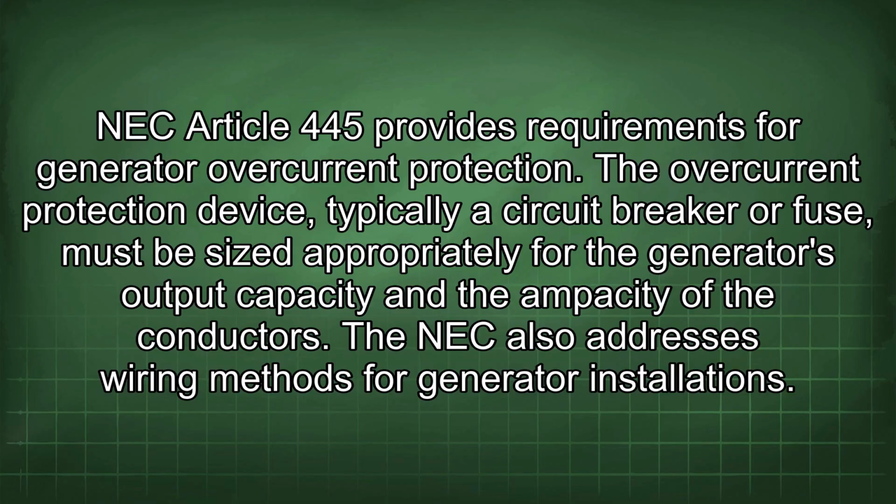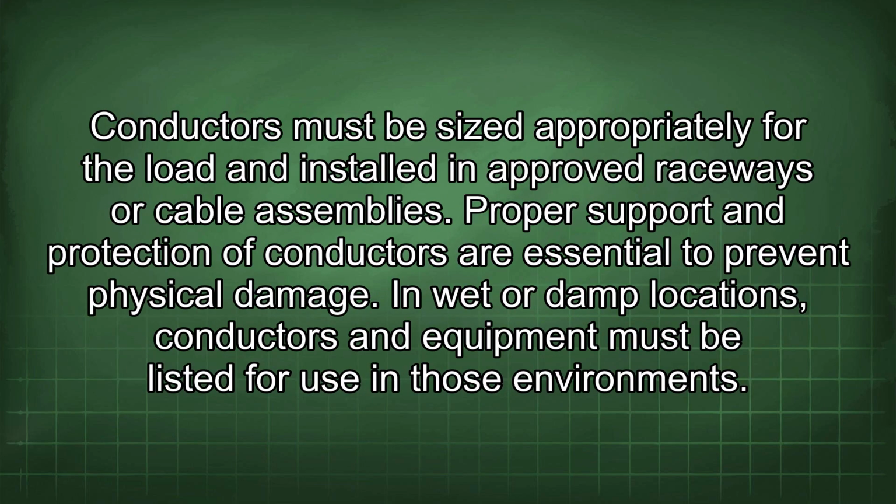The NEC also addresses wiring methods for generator installations. Conductors must be sized appropriately for the load and installed in approved raceways or cable assemblies. Proper support and protection of conductors are essential to prevent physical damage. In wet or damp locations, conductors and equipment must be listed for use in those environments.